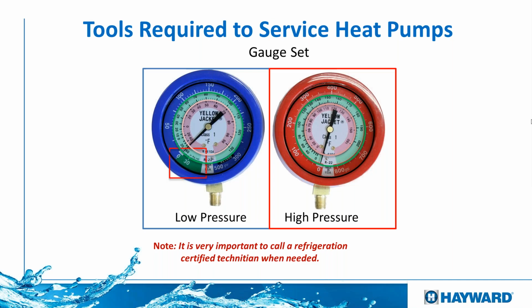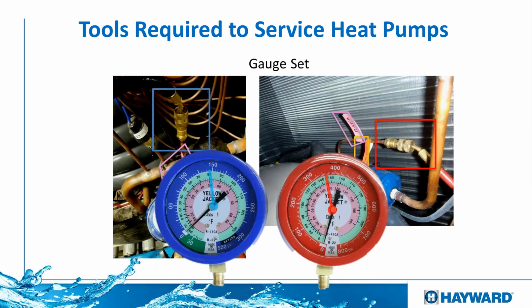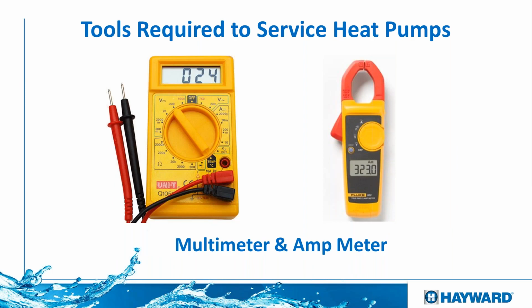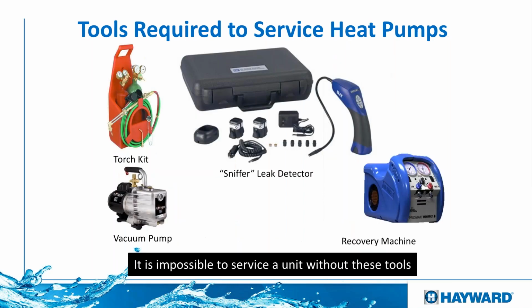We're going to need manometers. Those manometers are needed because we need to measure the refrigerant pressure, on the high or the low side, and our tech is going to go more into that. Then we are also going to need a multimeter and an amp meter in order to figure out exactly what kind of voltage we're getting on our unit and make sure that it is the appropriate voltage.